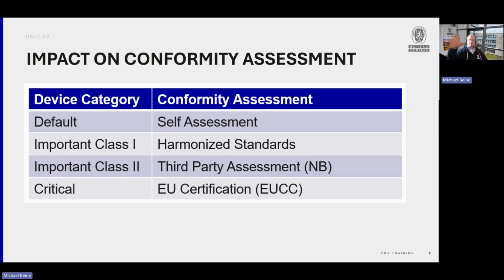The risk analysis will explain how the requirements of CRA Annex 1 are met and why they are met. And then there will be the standards. The standards will be used to create a test report to verify that the device implements the expectations of the standard. Together with additional information, like photographs of the devices from all sides, schematics, and architectural diagrams, the notified body makes up its mind if this product complies with the regulation.